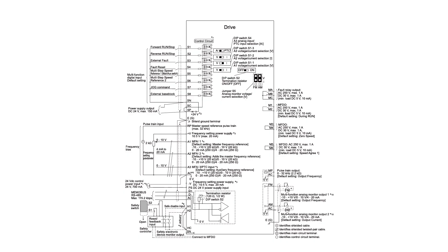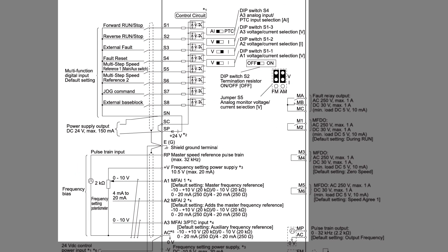Next is the control circuit wiring diagram for the GA-800. We will focus on this section. S1 through S8 create switched connections for various functions such as start, stop, and fault reset. Terminals +V, A1, A2, A3, and AC are for frequency reference inputs.